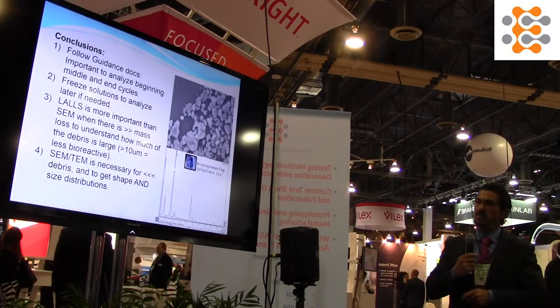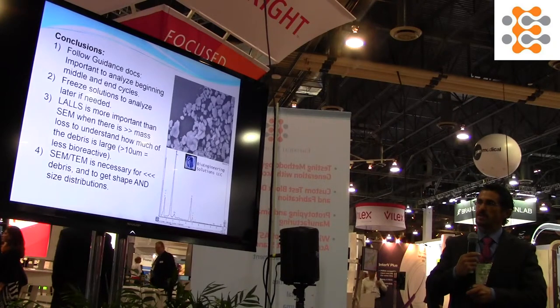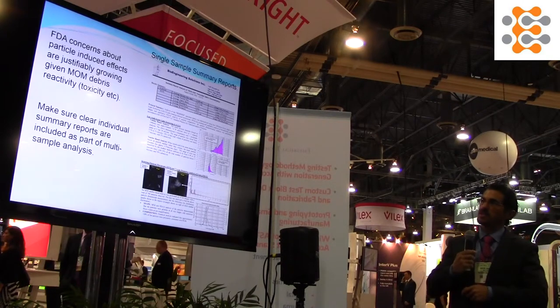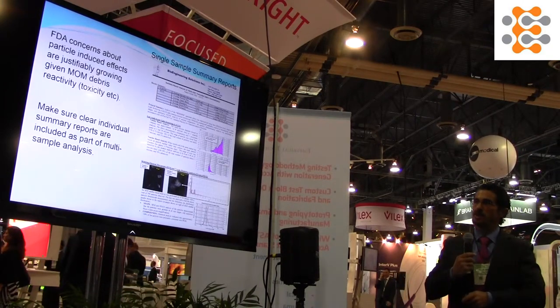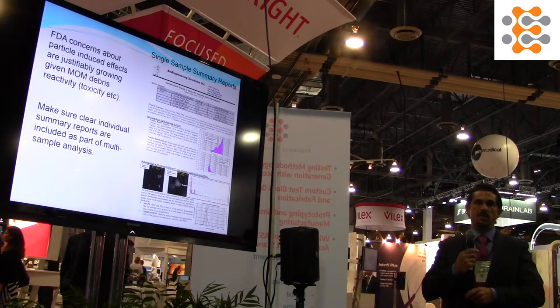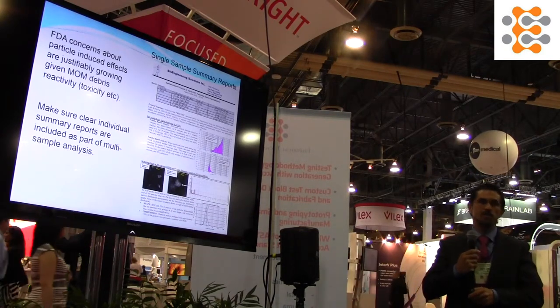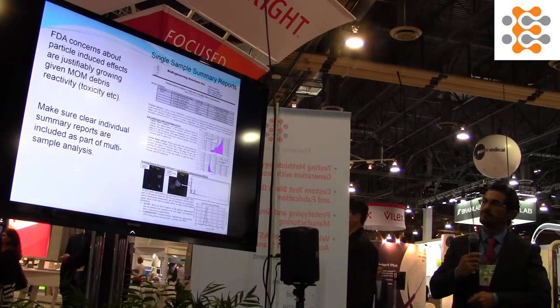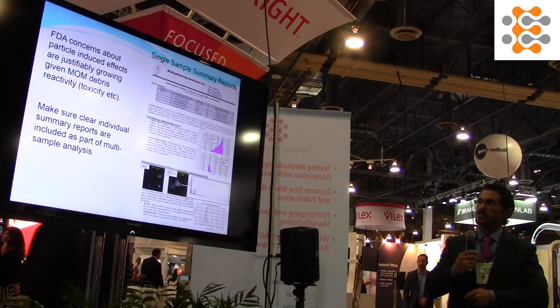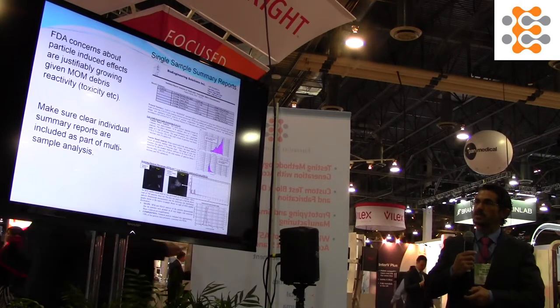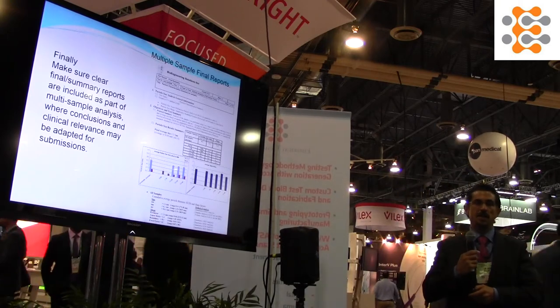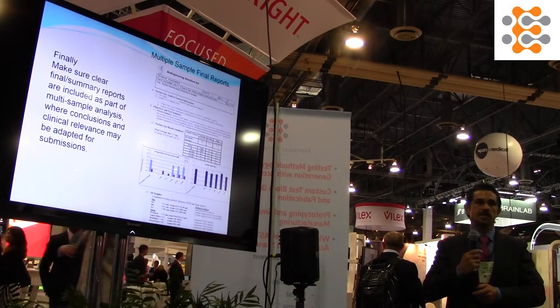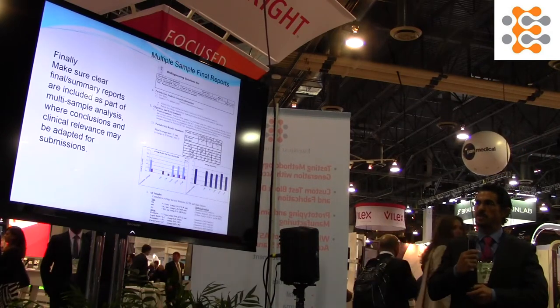However, SEM is necessary to get shape information. FDA concerns about particle-induced effects are justifiably growing, based on the metal-on-metal debris that relatively little in mass created a rather large response — enough that metal-on-metal hips are now less than 1% of the market. Make sure individual summary reports are included as part of a multi-sample analysis, and finally make sure that cumulative reports are also included so you can just cut and paste text for final submissions.